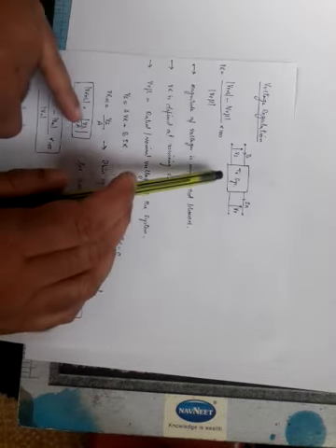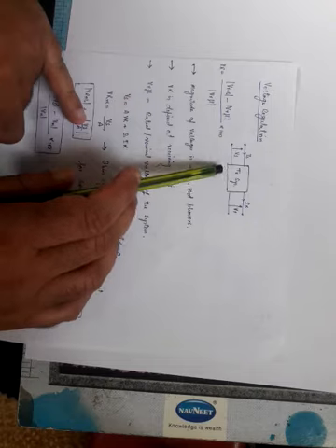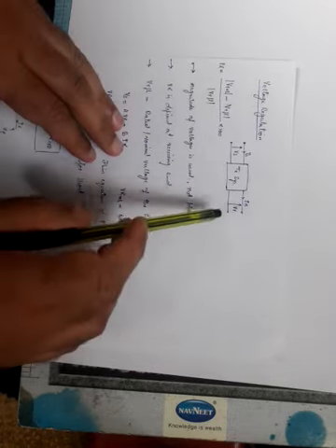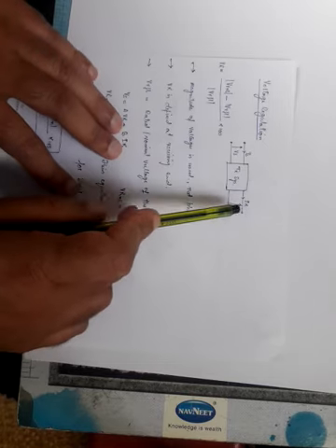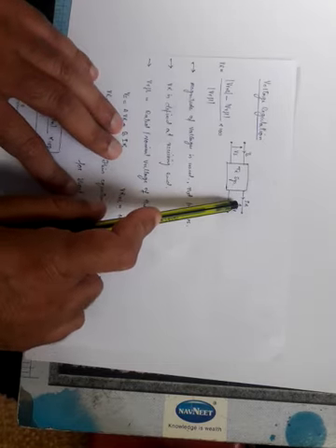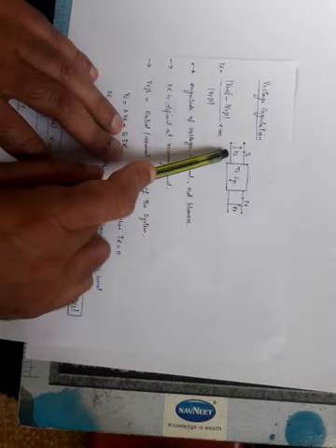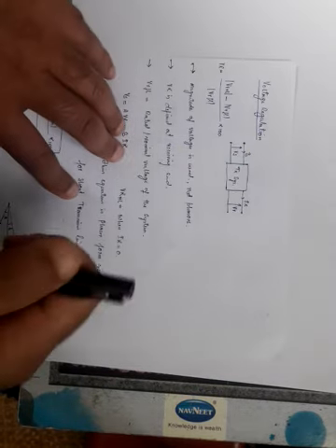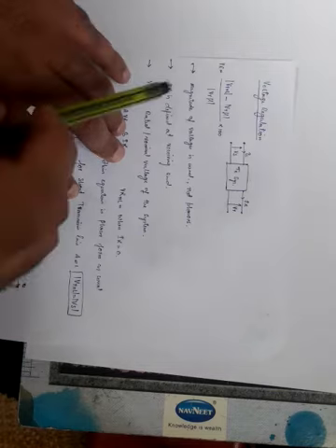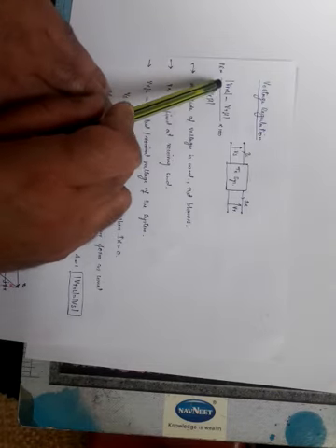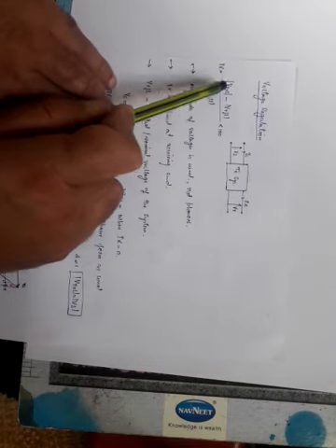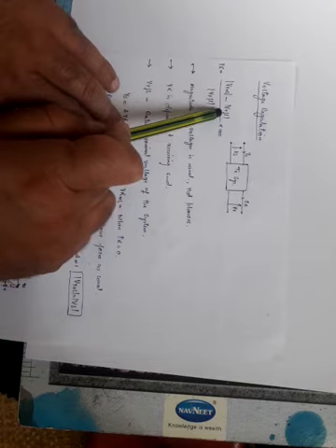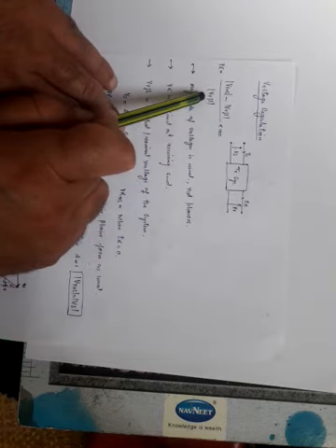This is a simple two-port network in which this box represents our transmission system or transmission network, where its output voltage is our receiving end voltage and this current is the receiving end current. Similarly, this is the sending end voltage and sending end current. In this case, we know that the voltage regulation is defined as receiving end voltage at no load minus receiving end voltage at full load, divided by receiving end voltage at full load.